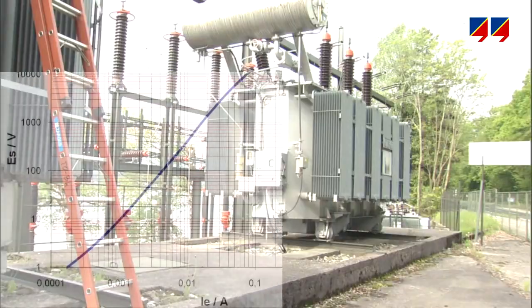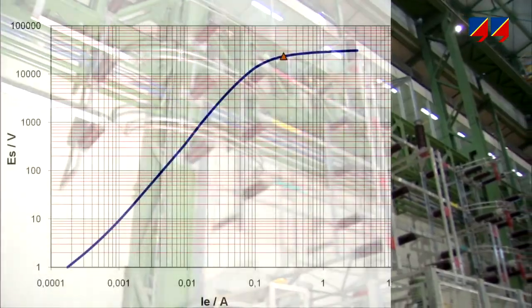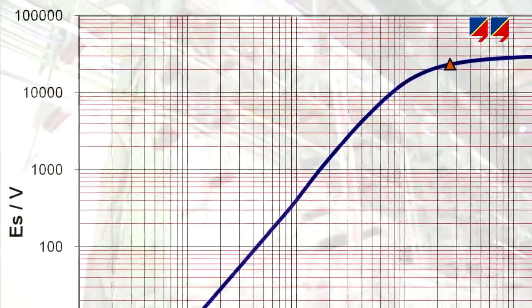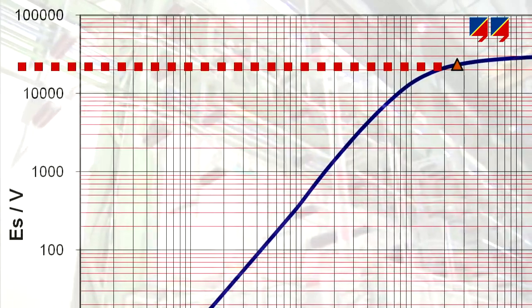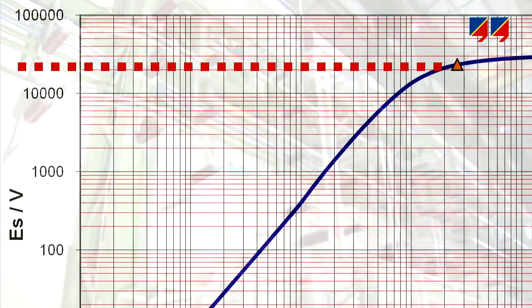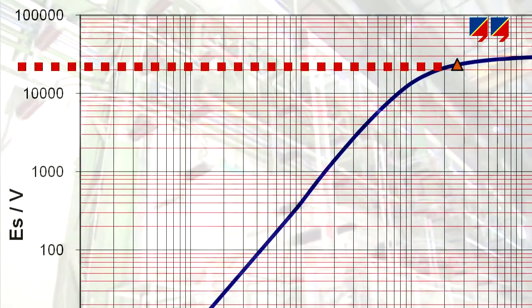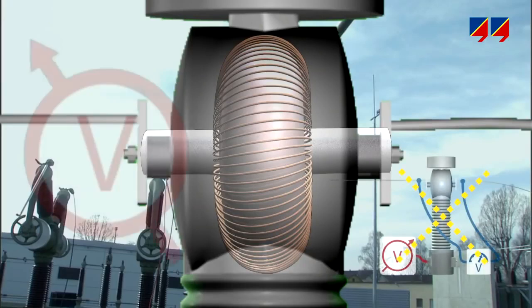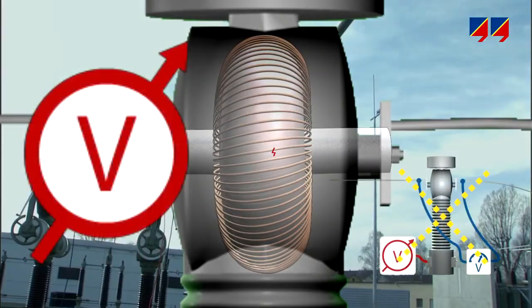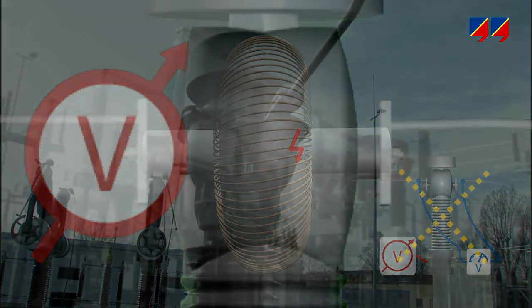In generator, transformer, or bus bar differential protection systems, CTs with knee point voltages of several thousand volts are used. These CTs cannot be tested with this method, since applying more than 4 kV to the CT's secondary winding would damage its insulation.